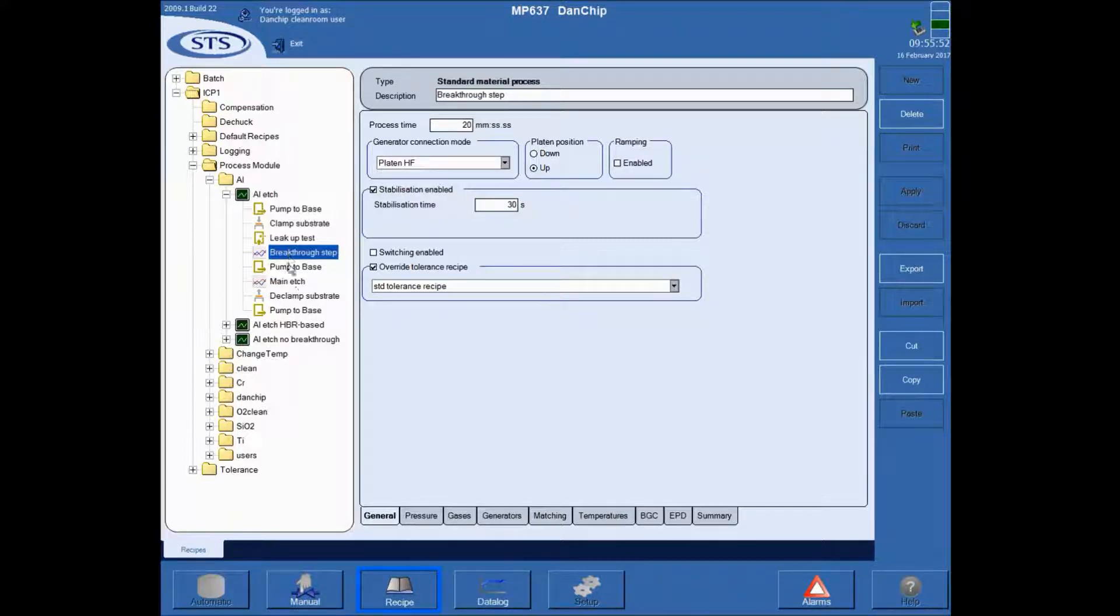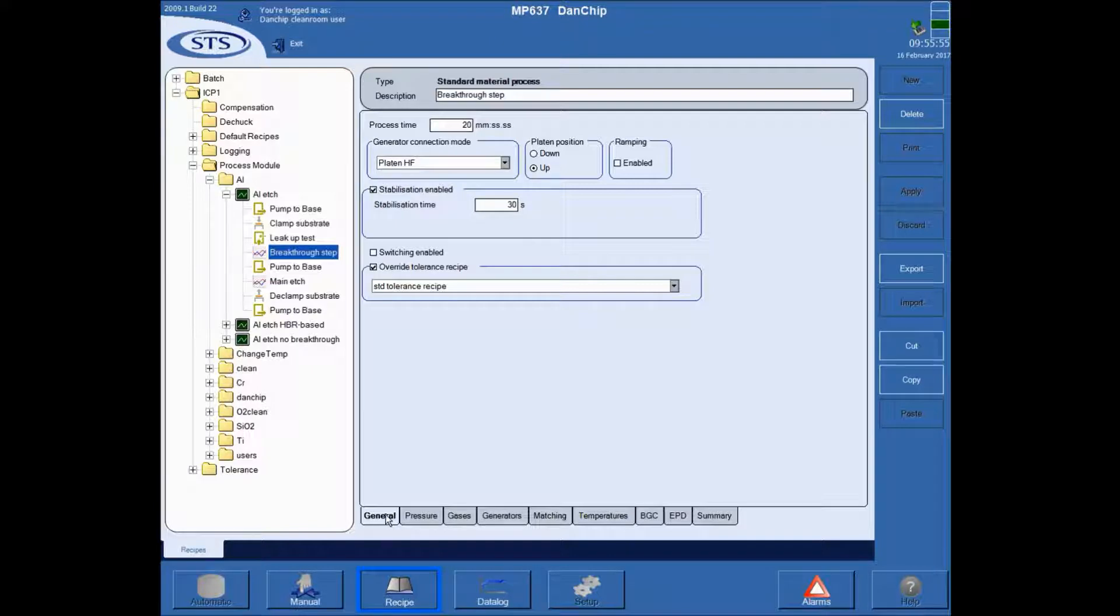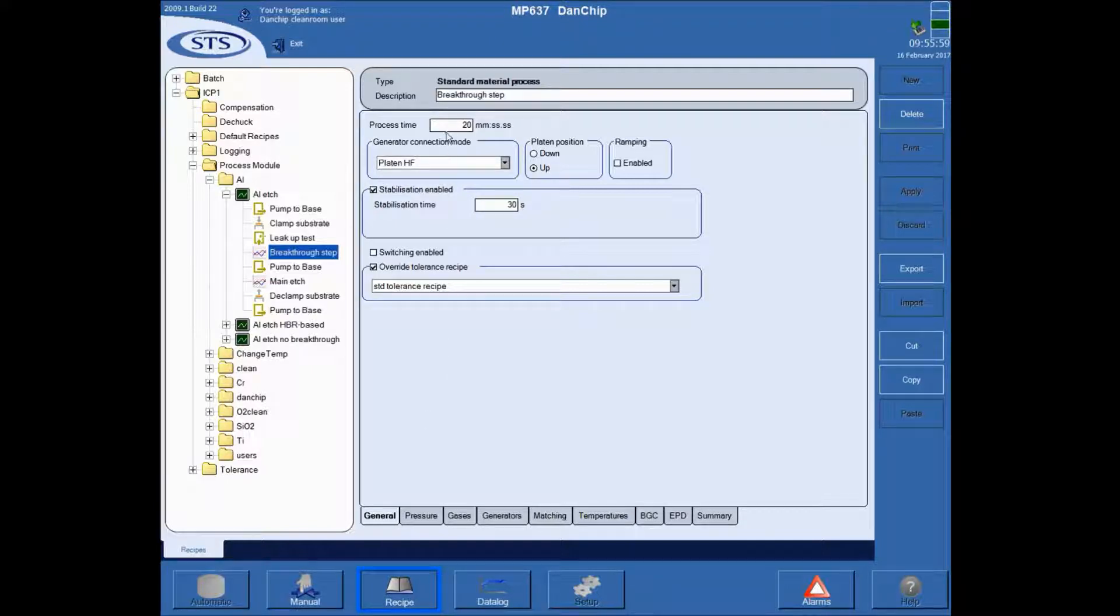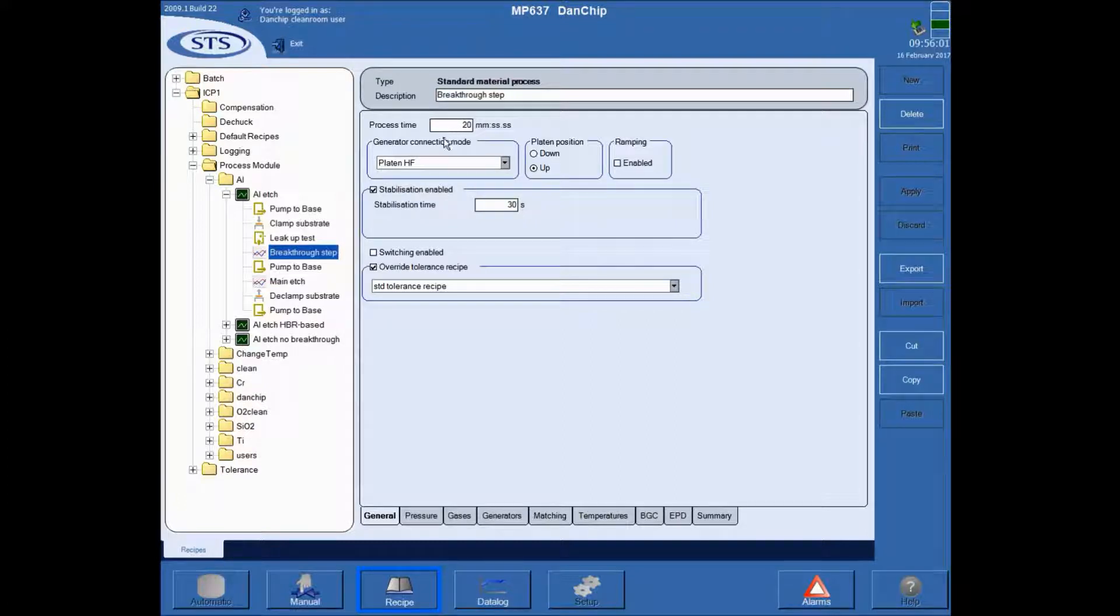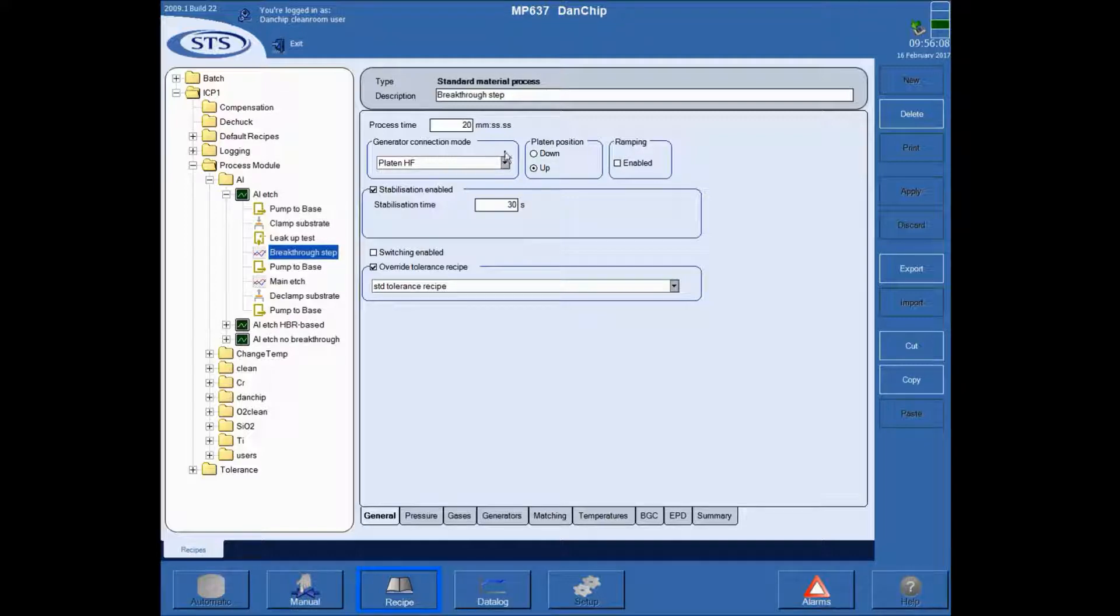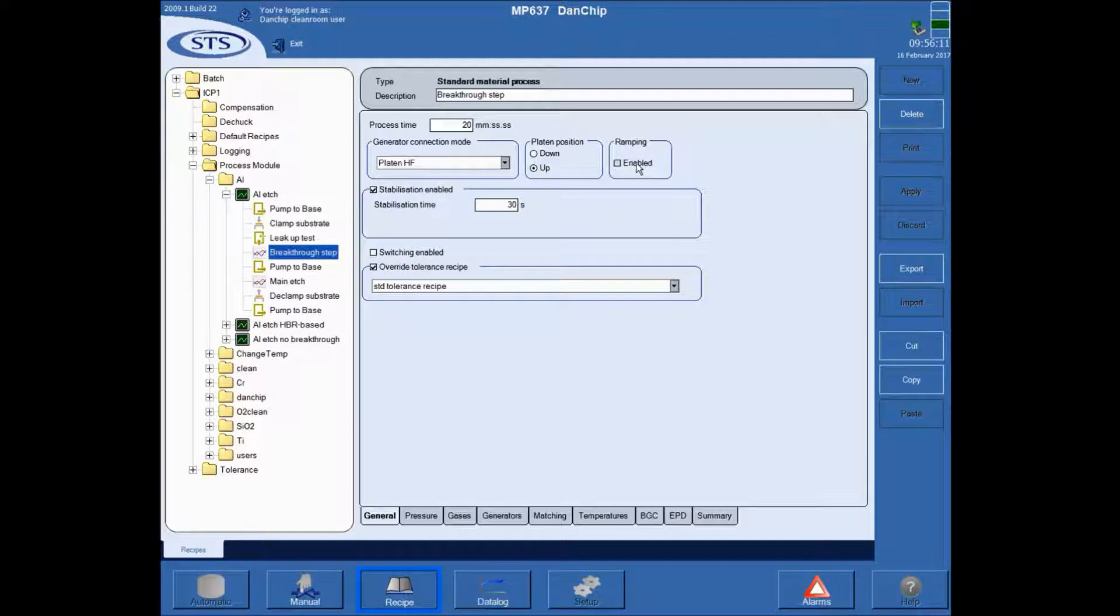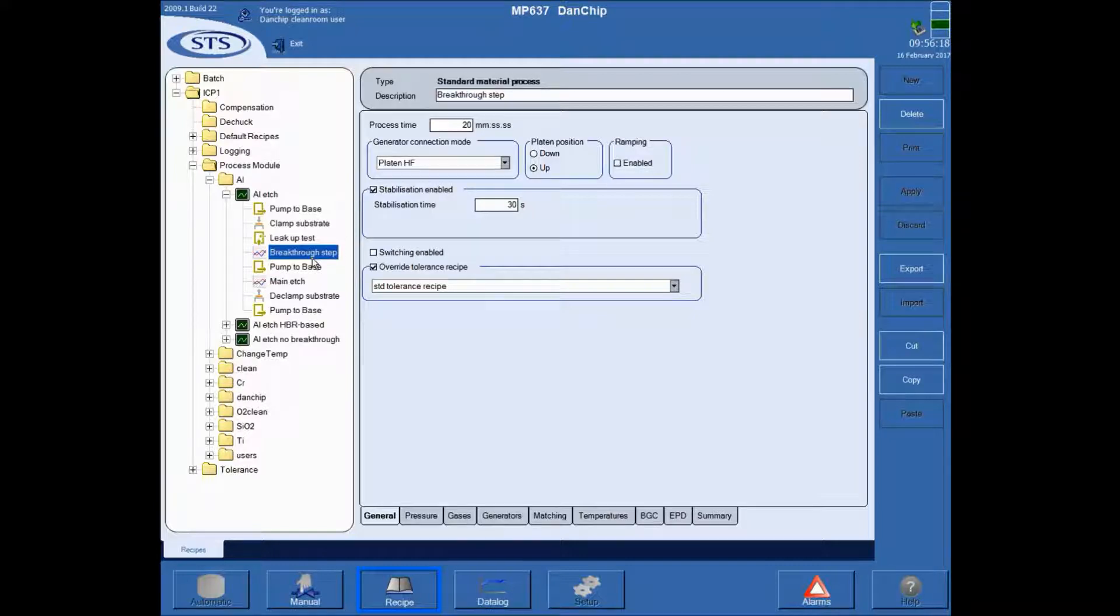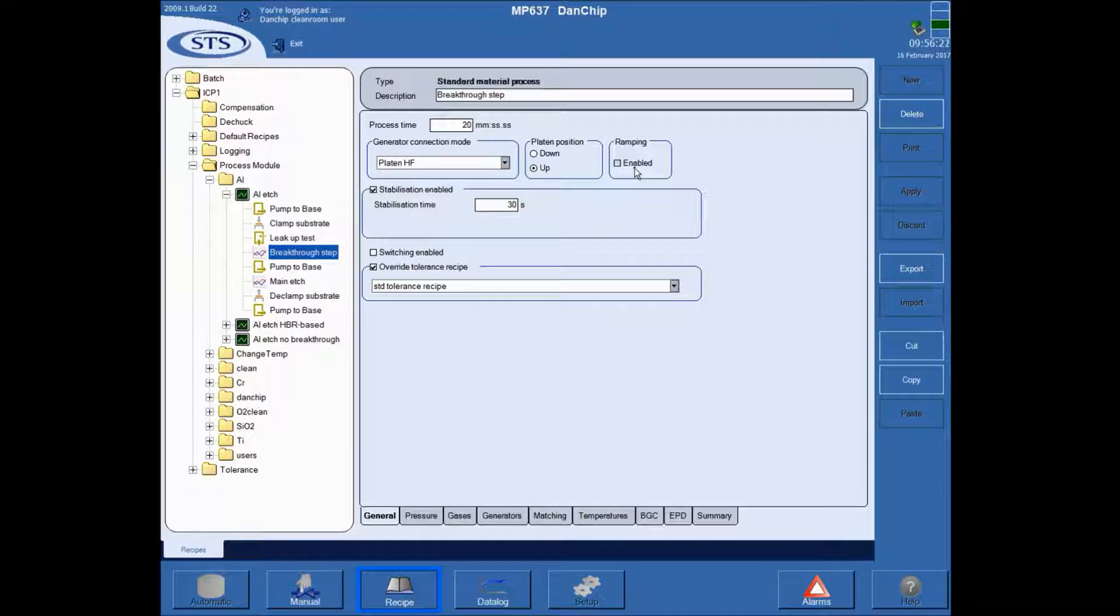In each of these process steps there is a number of tabs in which you can view or modify the process recipes. Under de-clamp, you will de-clamp the wafer from the electrode and pump to base ensures that everything is fine. So first of all in the breakthrough step there is this general tab in which you indicate the process time. There is some settings for the generator and the platen up. You typically don't want to change those. The ramping is not used a lot because it enables you to ramp parameters up and down during this individual step. It makes the process parameter space quite complex.